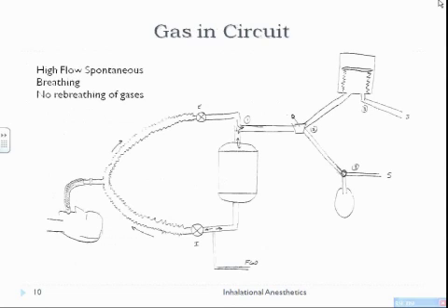Okay. So let's see what happens if you're at a high gas flow rate on emergence. When you have that person spontaneously breathing at the end and you want them to get that gas off, this is what you do. You go to 10 liters per minute, and now the gas is coming in pretty fast. Okay, but part of it goes forward. If I'm pulling 3 liters per minute, only 3 liters of the gas is going forward, and 7 liters is going to go backwards. It's simple math. It only needs 3 liters to keep the system moving. So if I don't use it, then the other 7 liters is going to go somewhere else. And it's going to find the area of least resistance, which is going backwards.